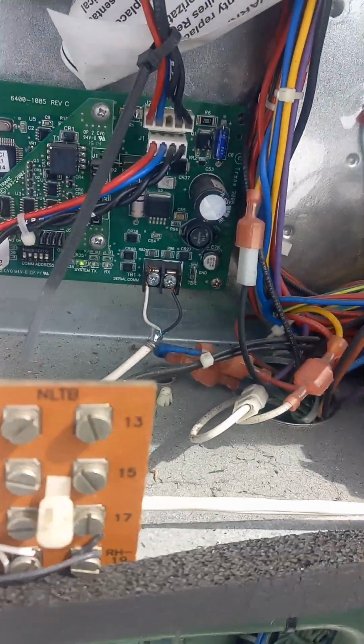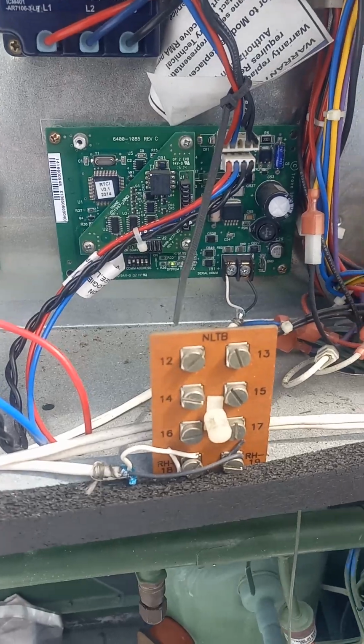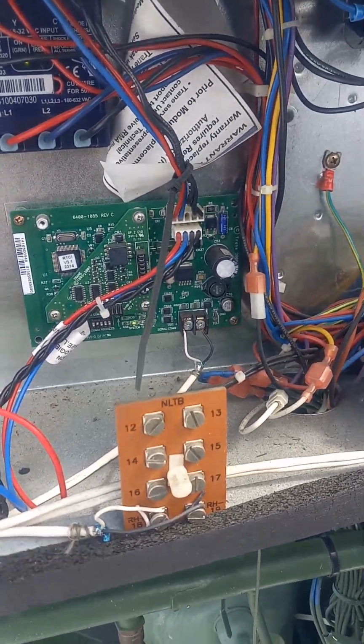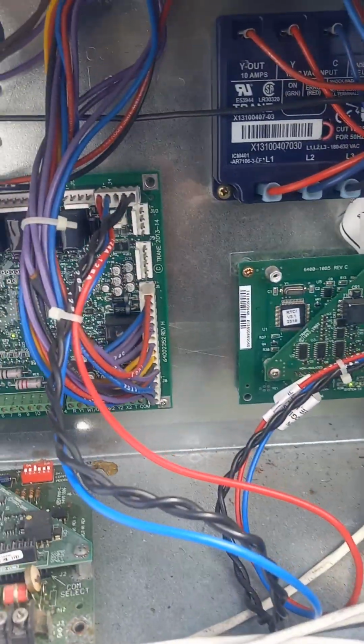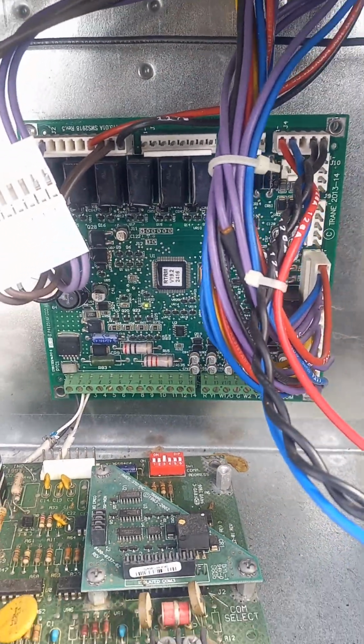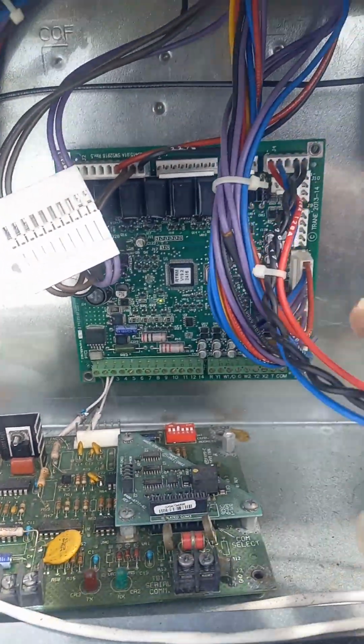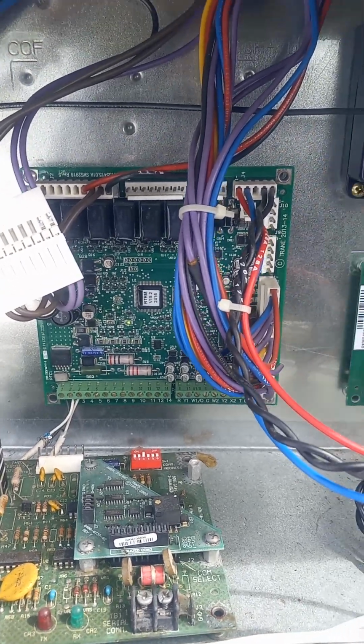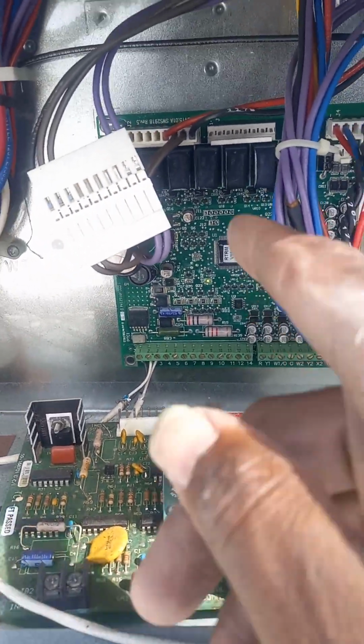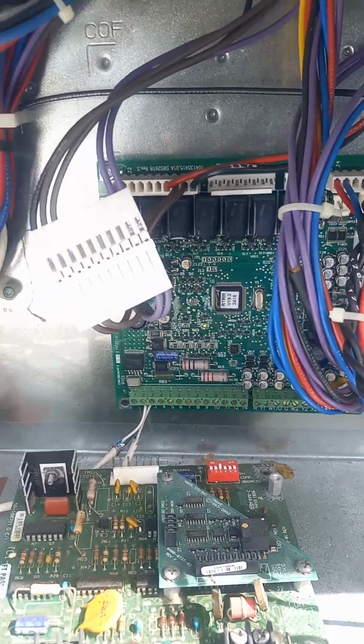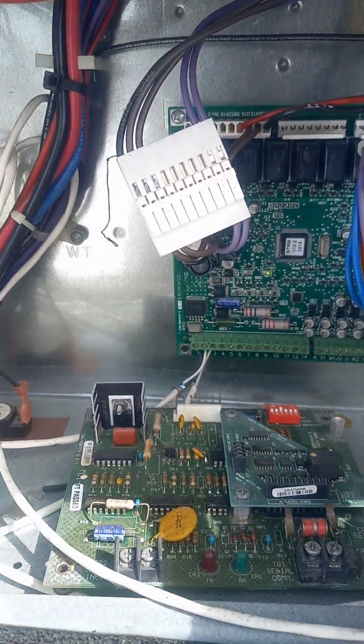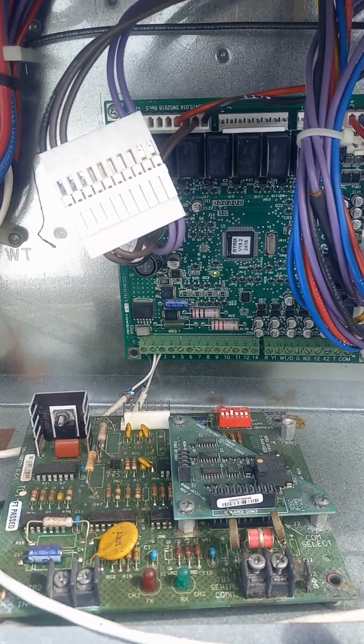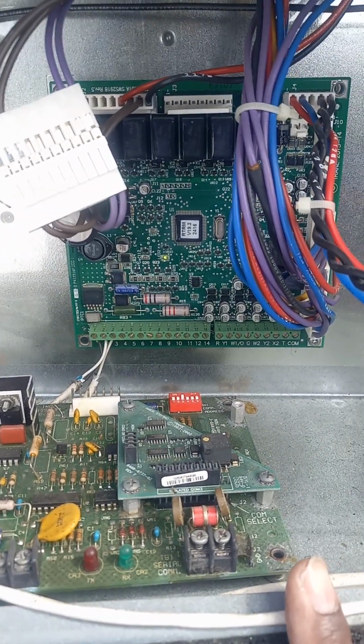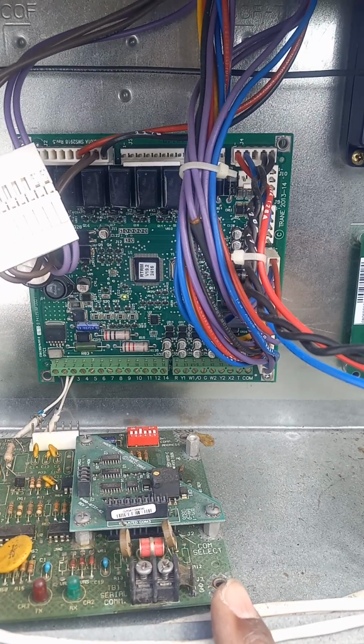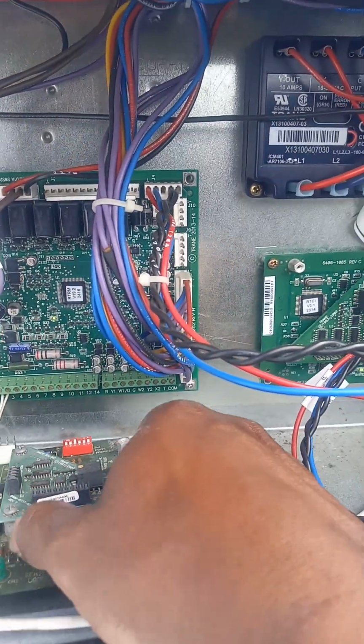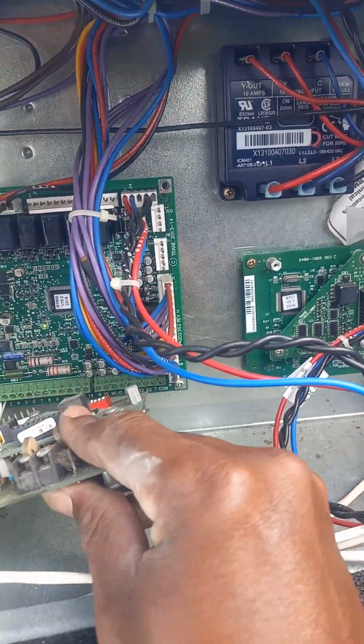So this communication board is different from the one I was showing from the AN unit. That's a different thing. What's actually controlling the unit is this RTRM board. All the low voltage has to go through here to operate this unit. If this goes bad, the unit's not going to operate. On this board, you can have communication, or you can have an actual thermostat that you install in it. Move this out of the way. Somebody installed something and just left it.